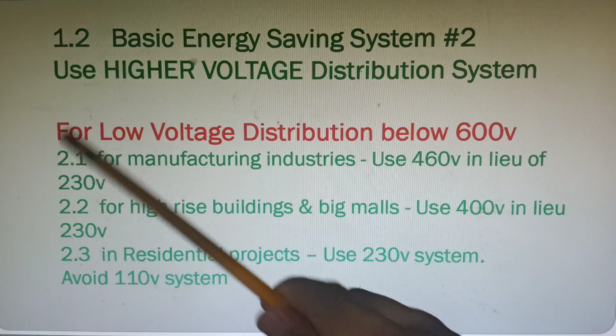Okay, number 2, 1.2, basic energy saving system number 2, use higher voltage distribution system. Again, when we're talking of distribution in the plant, in the building, or in the malls, then it is always better to adopt a higher voltage than let's say a lower voltage. So 460 volts secondary distribution is much better than 230 volts distribution system. And for high-rise buildings, 400 volts system is much better than the simple 230 volts distribution system.